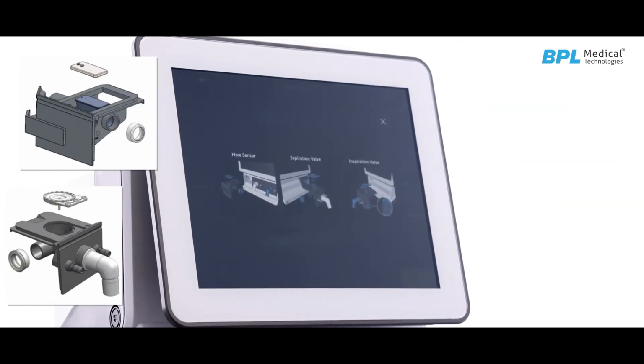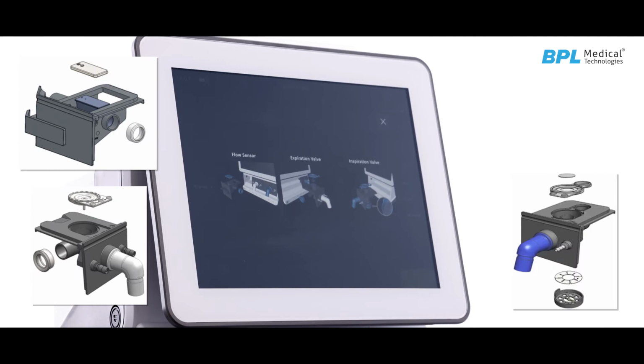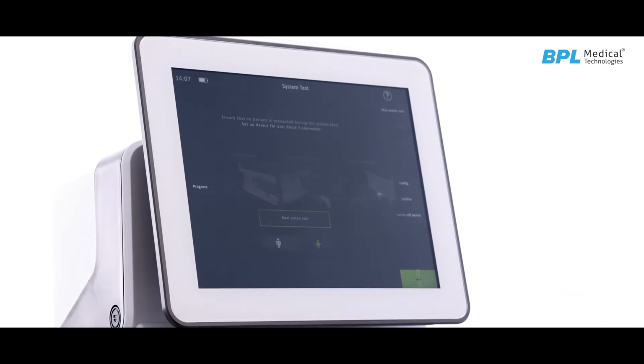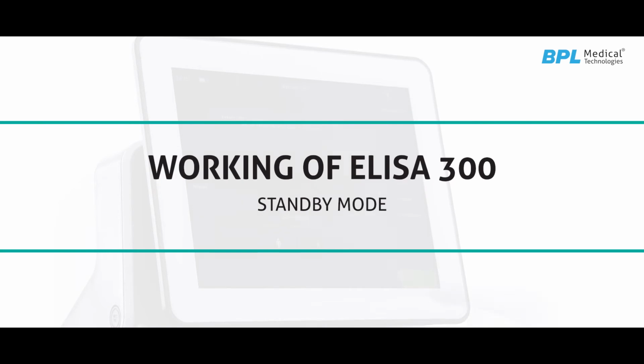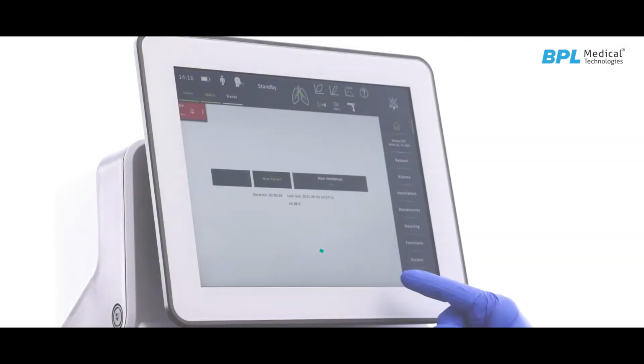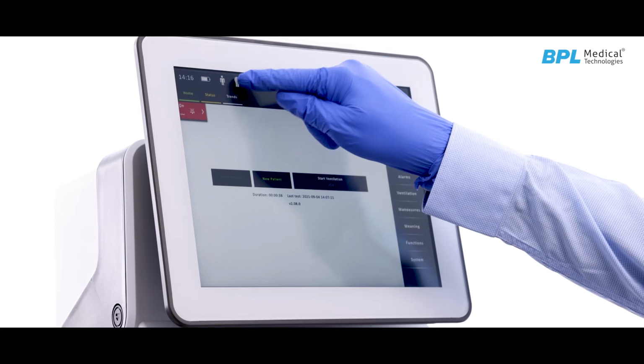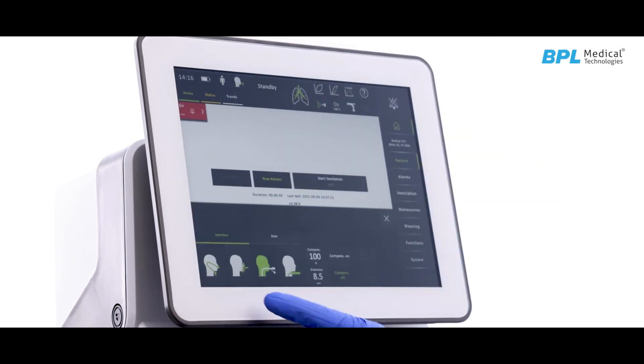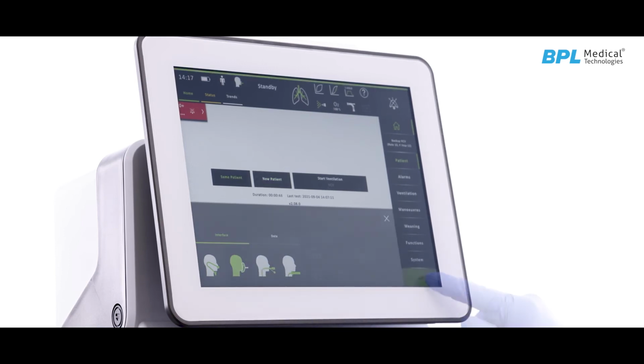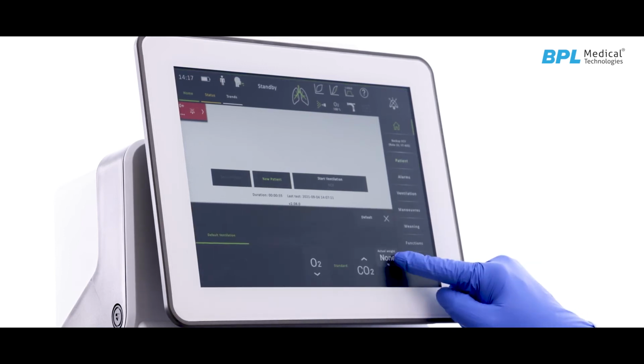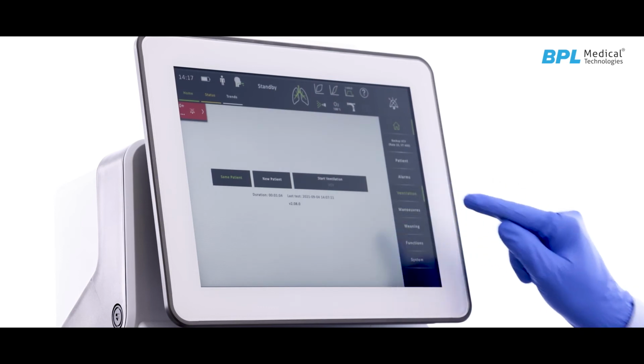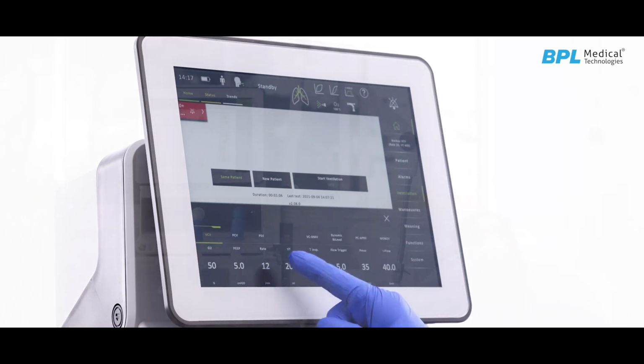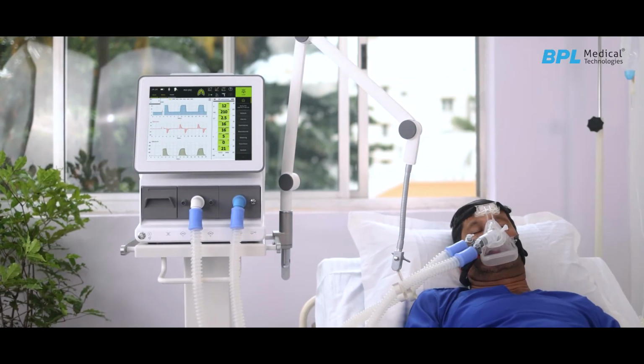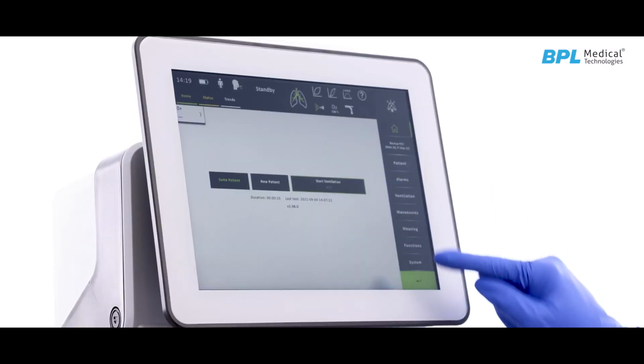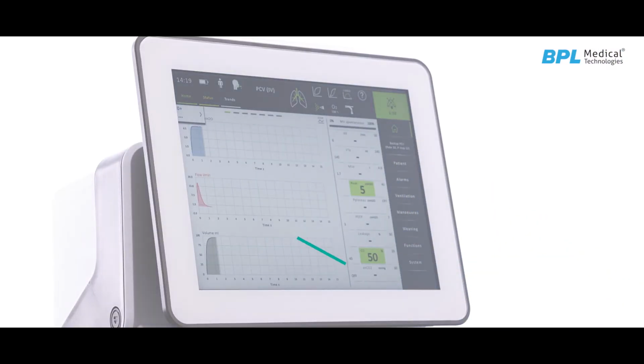A detailed pictorial representation of the inspiratory and expiratory valve or sensor assembly is provided. After completing all the tests, the user will enter standby mode. Here, the user will have the following options to select: type of ventilation, new patient with ideal body weight calculator, and ventilation mode. If no input is given, then the ventilation can be started with default settings. Press the start button and enter to initialize the ventilation.